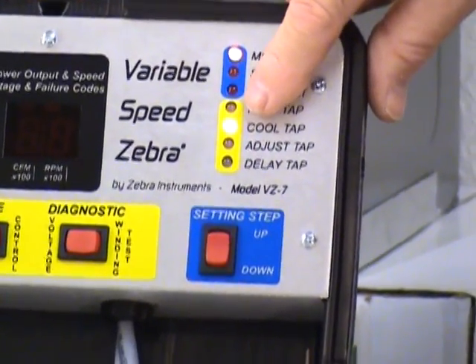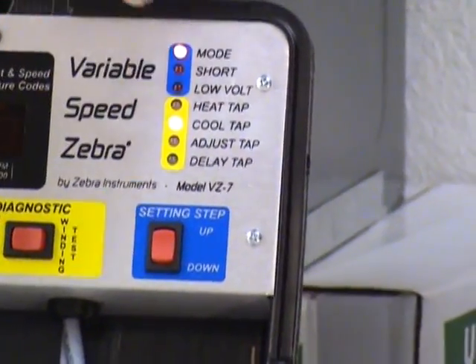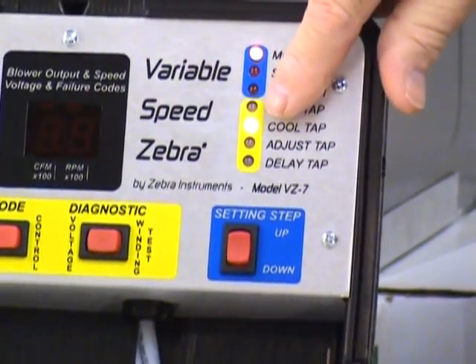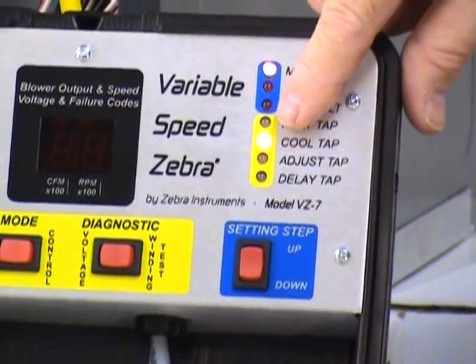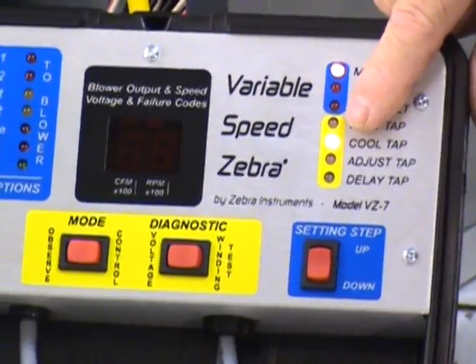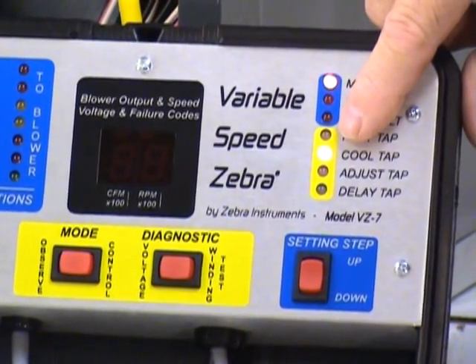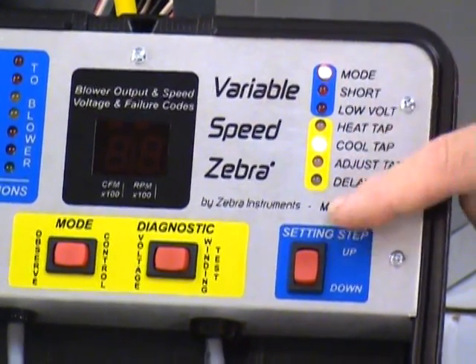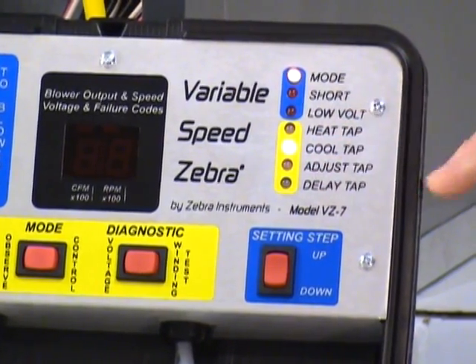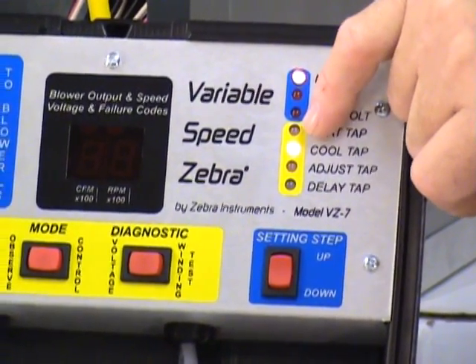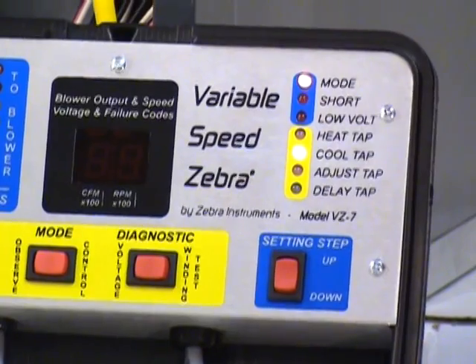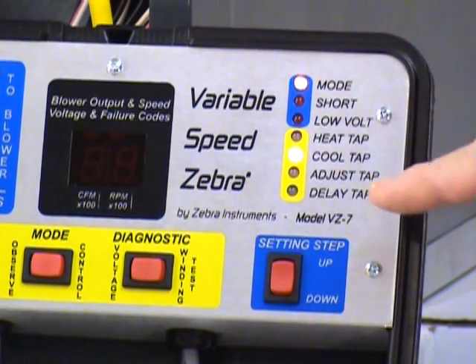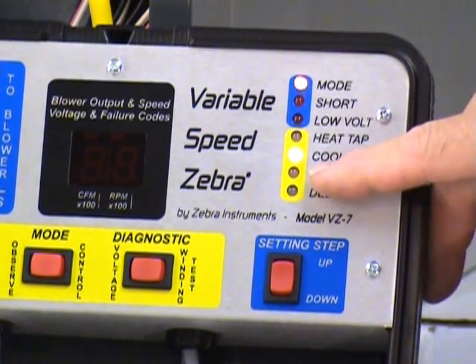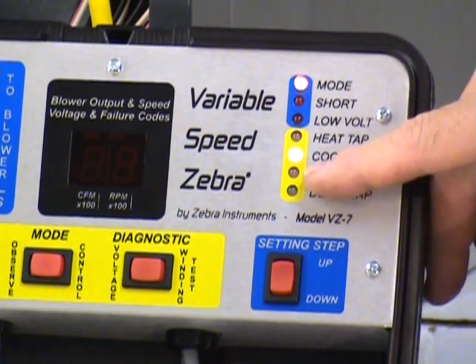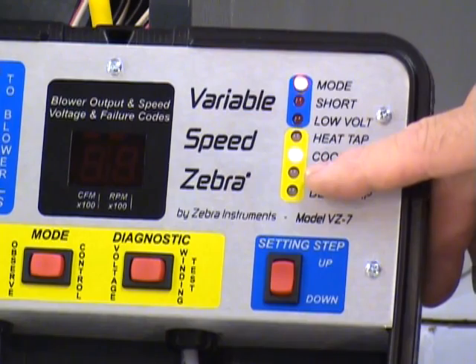And if this light is yellow, and you kind of got to look at it straight on to see the yellow light, it's not as clear cut as you'd like it to be, but if it's yellow, then that means both switches are activated. So if you're familiar with that manufacturer and you see that the heat tap is red, you know at an instant that it's set up for a certain thing. If the adjust tap is yellow, you know that it's set to run at the highest speed that that particular air handler could possibly run at.